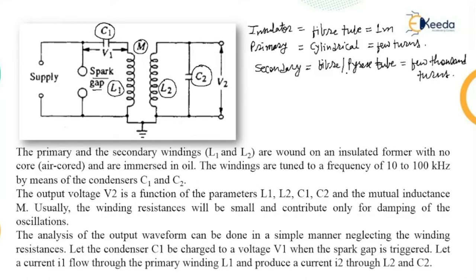The whole assembly is immersed in oil — both windings are immersed in oil under certain pressure — with separate bushings taken out for the primary and secondary windings. The primary winding is supplied through a high voltage capacitor rectifier unit rated for 10 kilovolt to 50 kilovolt and more, and the power rating of the transformer is 10 kVA or more. The output voltage V2 is a function of the parameters L1, L2, C1, C2, and the mutual inductance M.